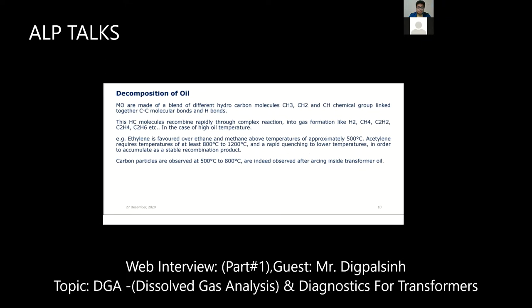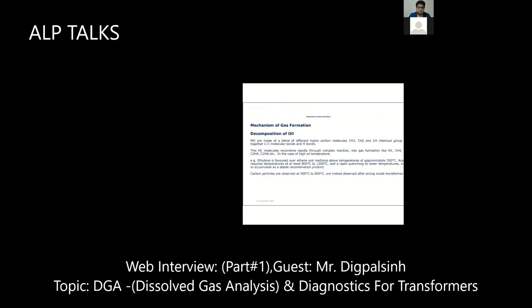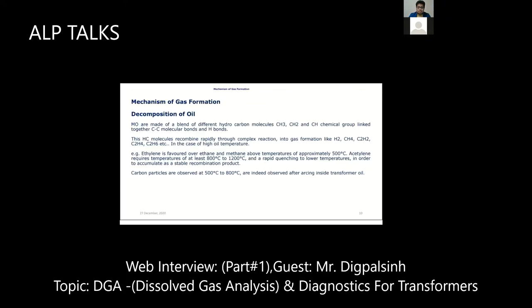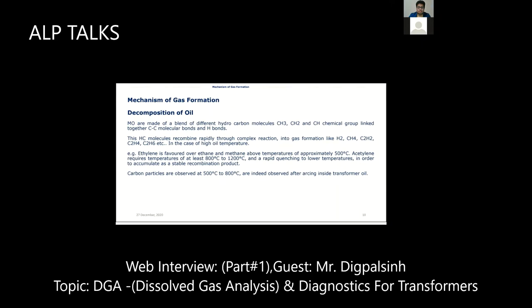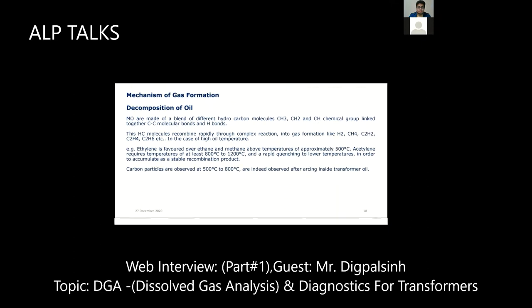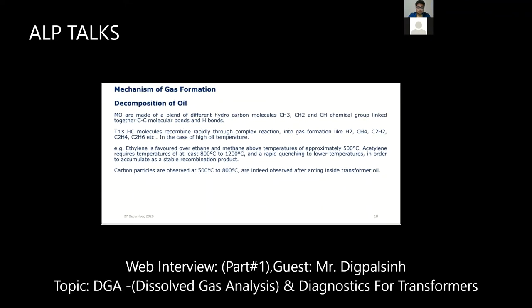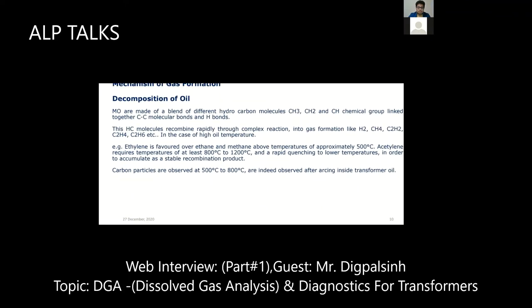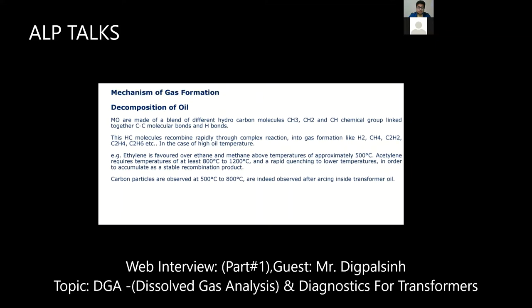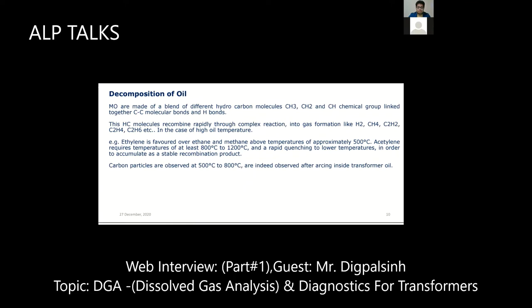Particularly ethylene, you will see it is the thermal fault in oil because of decomposition of oil. The major gas is ethylene. If in your DGA result ethylene is high, then you can say there is decomposition of oil because of thermal fault. And the carbon oxides, CO and CO2, are also involved if temperatures go beyond 500 to 800 degrees Celsius.